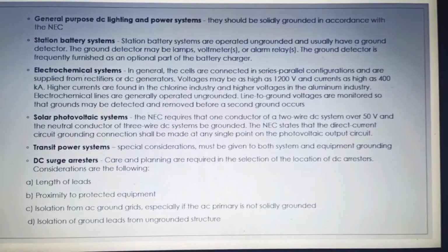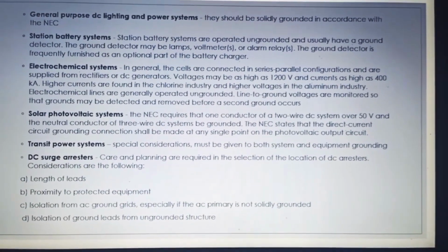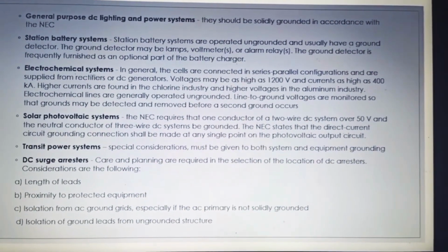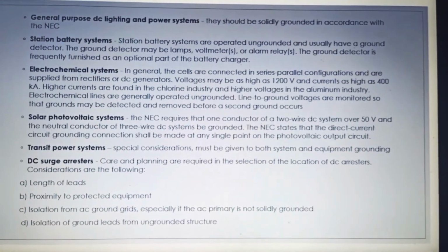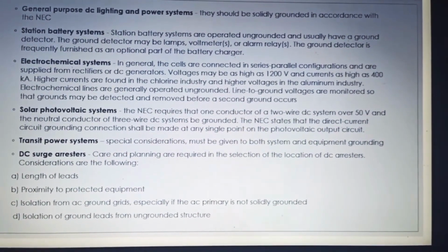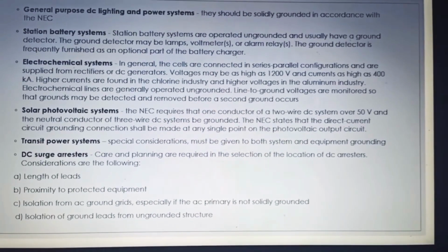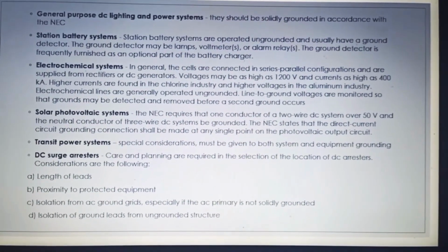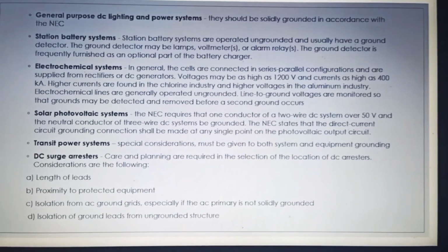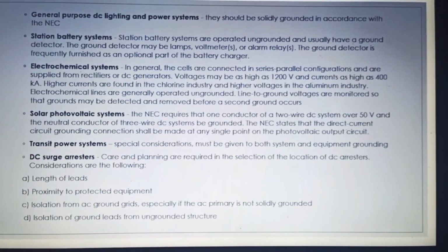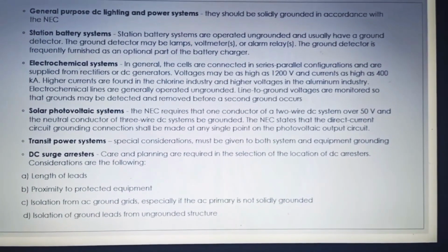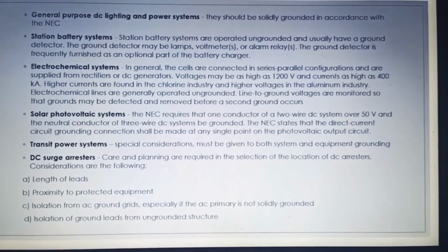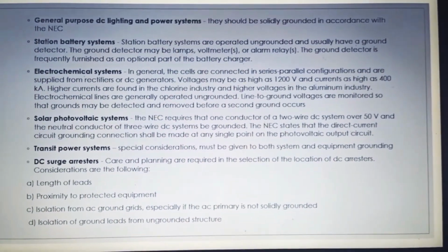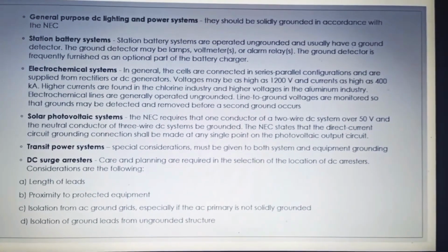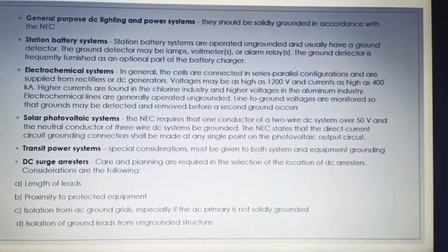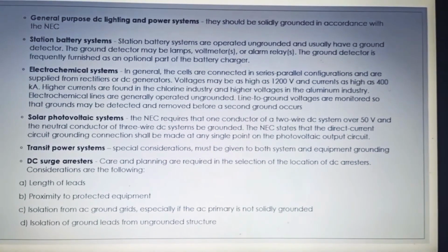Line-to-ground voltage is monitored so that a ground may be detected and removed before a second ground occurs. Some higher voltage DC pot lines in aluminium smelters may be grounded through a fuse, which is monitored. The fuse blows on the first occurrence of a ground fault and an alarm is sounded. Operators and maintenance personnel ordinarily work on electrochemical systems while the system is energized. Safety information may be found in IEEE Standard 463.